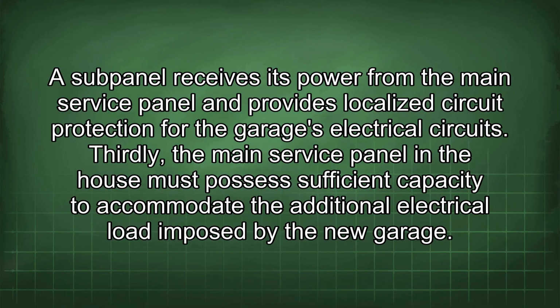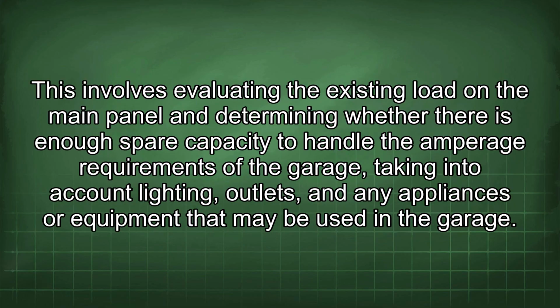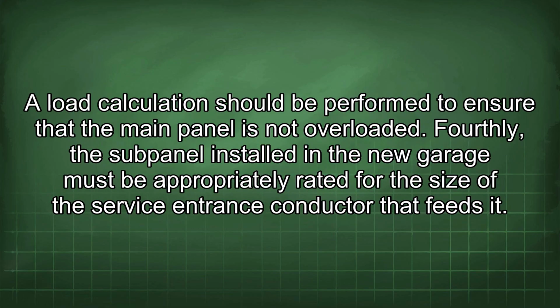Thirdly, the main service panel in the house must possess sufficient capacity to accommodate the additional electrical load imposed by the new garage. This involves evaluating the existing load on the main panel and determining whether there is enough spare capacity to handle the amperage requirements of the garage, taking into account lighting, outlets, and any appliances or equipment that may be used in the garage. A load calculation should be performed to ensure that the main panel is not overloaded.